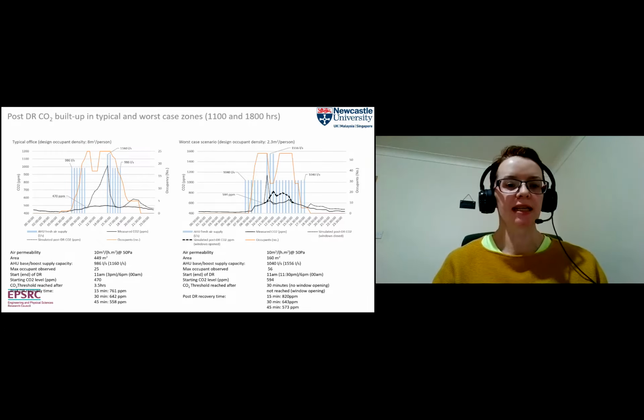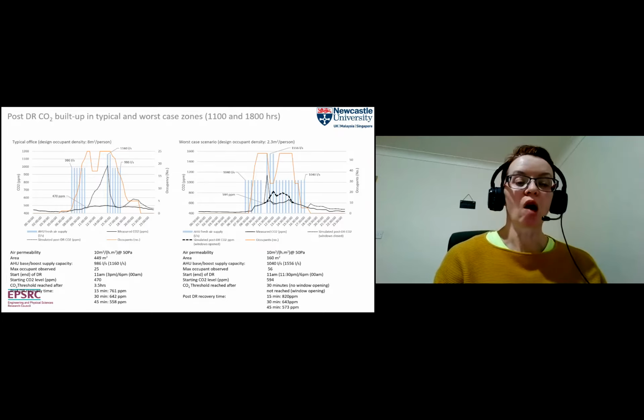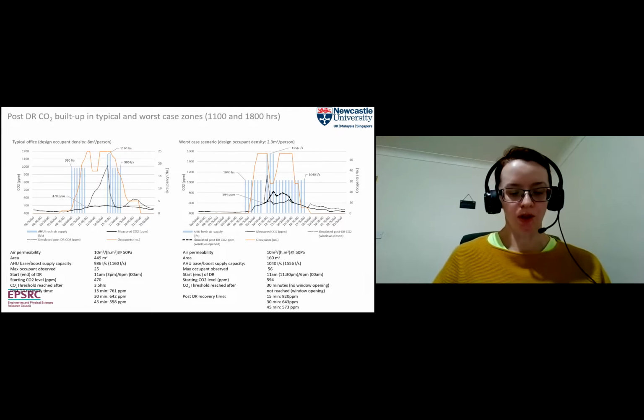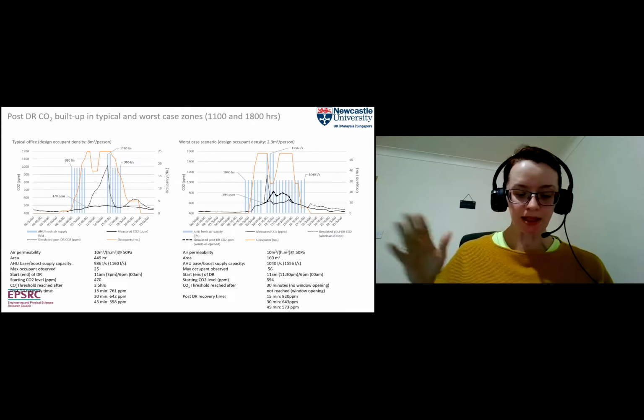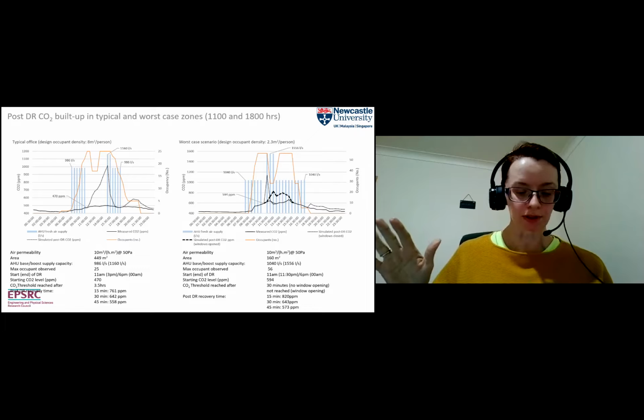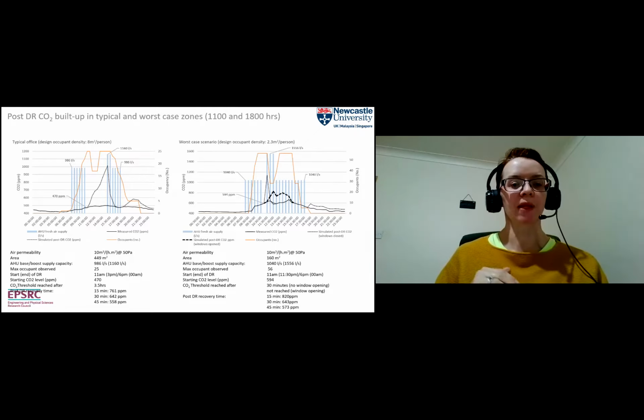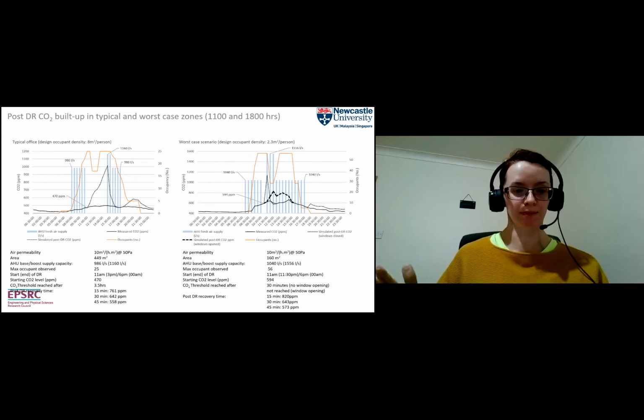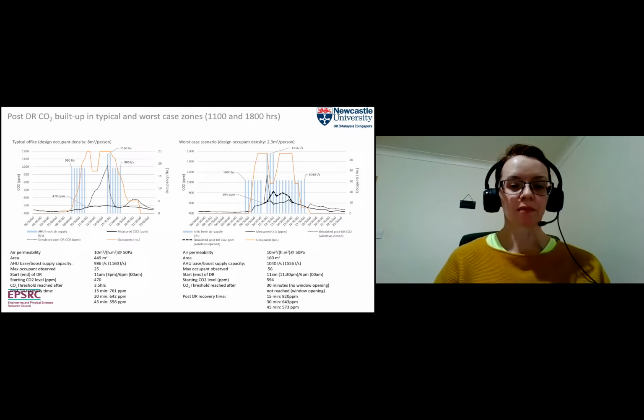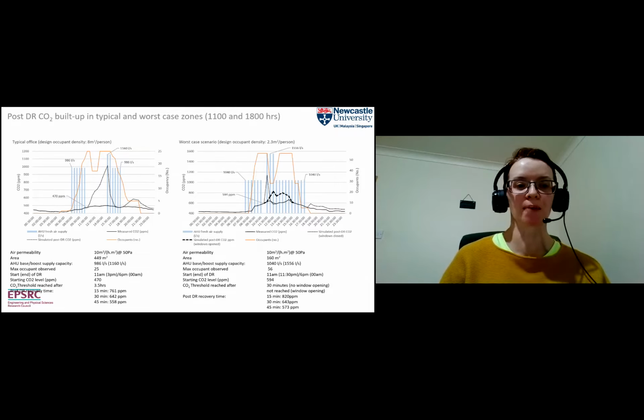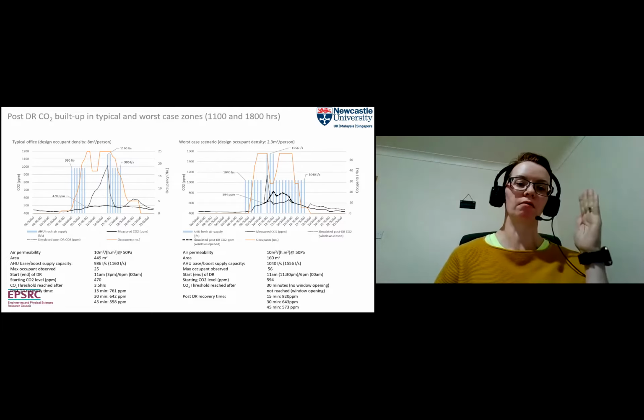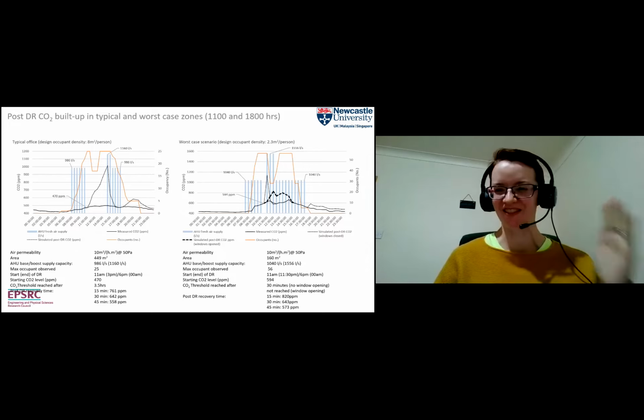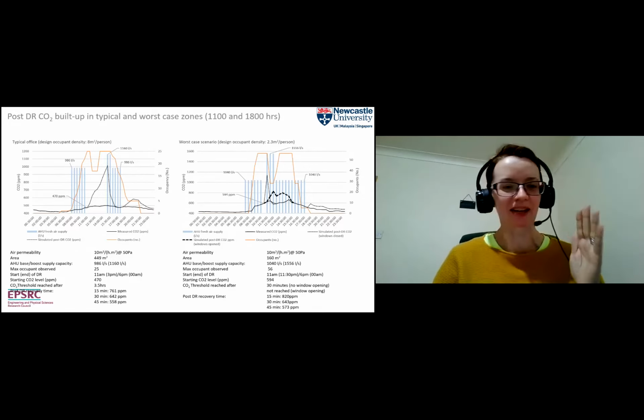What we've looked at here is our carbon dioxide sensors. So the carbon dioxide is monitored throughout the building. There's tens of carbon dioxide sensors. And the mechanical ventilation is there to ensure that there's sufficient fresh air to keep the carbon dioxide levels below 1,000 in terms of the measured CO2 in parts per million, which is the left-hand axis of the graph. I had to wave my hand there to remember left and right.